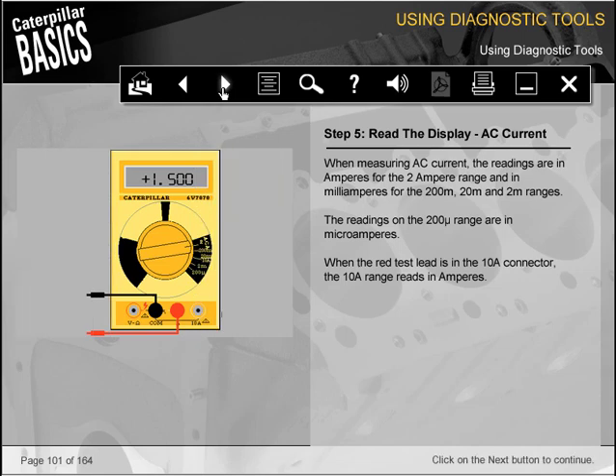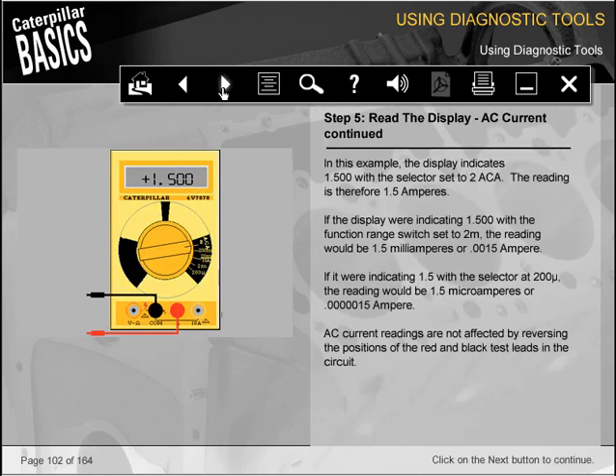When measuring AC current, the readings are in amperes for the 2 ampere range and in milliamperes for the 200m, 20m, and 2m ranges. The readings of the 200µ range are in microamperes. When the red test lead is in the 10A connector, the 10A range reads in amperes. In this example, the display indicates 1.500 with the selector set to 2 ACA. The reading is therefore 1.5 amperes.